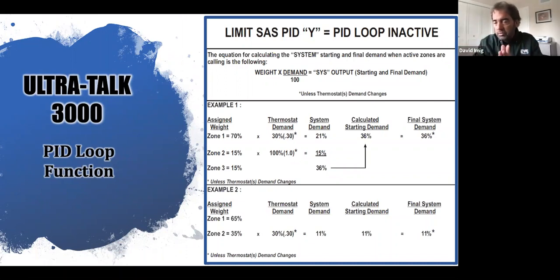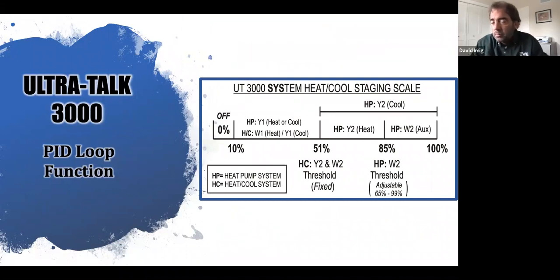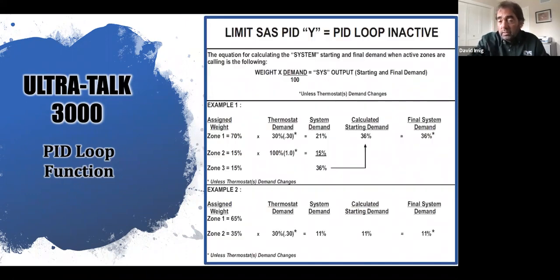And this is what happens, and I'm showing you this so that you know exactly what happens. You'll see that I do not have the multiplier of 3 anymore. I'm going to get a system demand of 36%, and that's where I stay. I cannot go any higher. So I go to 36%. That means I'm in first stage on multi-stage. I cannot go to second stage. Now that may be fine. However, if I'm in that large zone, like you see, the 70% weighted zone, and my homeowner is using a setback, and it's a worst case scenario, heating or cooling day where it's very hot or very cold, and I've got a lot of temperature to recover, I've got to do that in first stage.